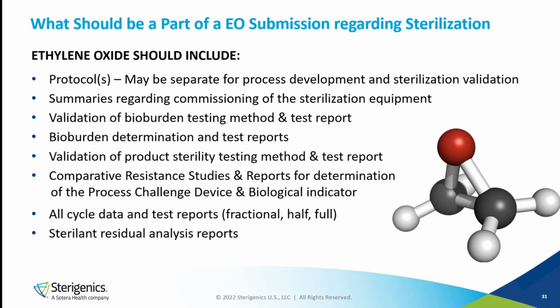For EO processed, you need an explanation and rationale on how your bioburden has been determined, how you control your bioburden, and how everything has been validated, first things first. Product sterility: you also need to define and explain the product sterility report and how you have validated that part. Comparative resistance study, so it's the PCD that I mentioned before, how you have selected your PCD for your validation, and then for sure the entire validation, fractional and half cycle, and data. Without forgetting the residue part, like the example that I explained a few minutes ago, where you have to define the right EO limits.